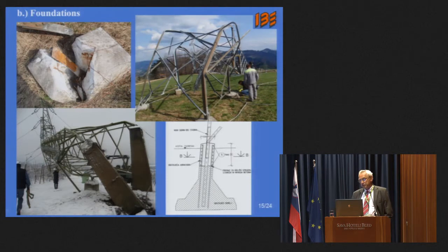About foundations, this was the best solution for us. The foundation hasn't been damaged, so we can put a new steel structure on the old foundation. Another one is this, where only the head of the foundation was damaged, and the worst was this, where the foundation was pulled out.